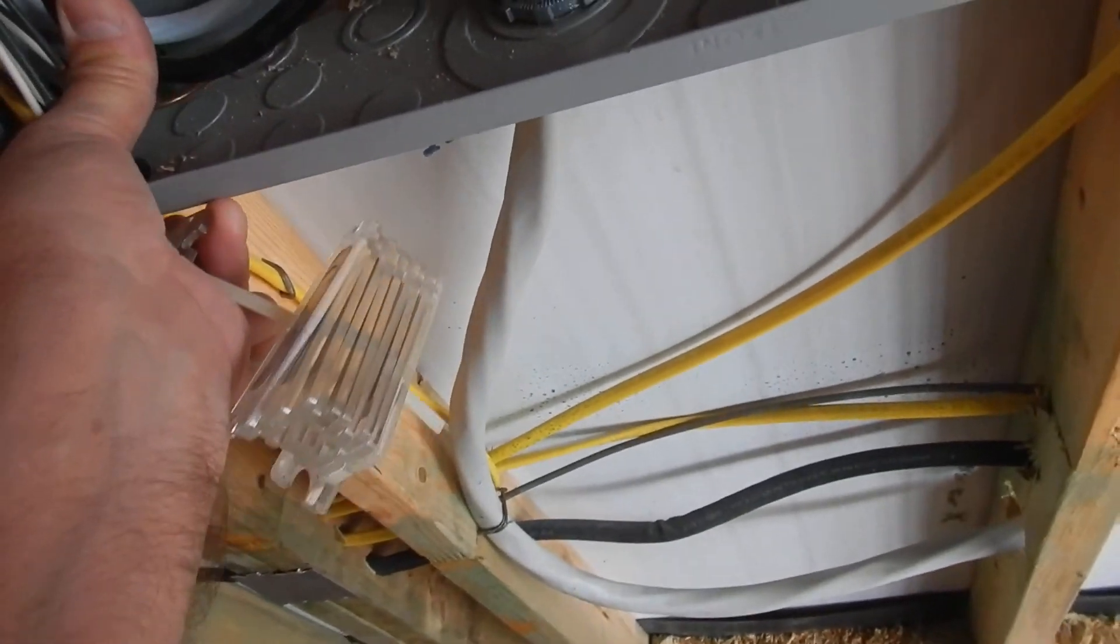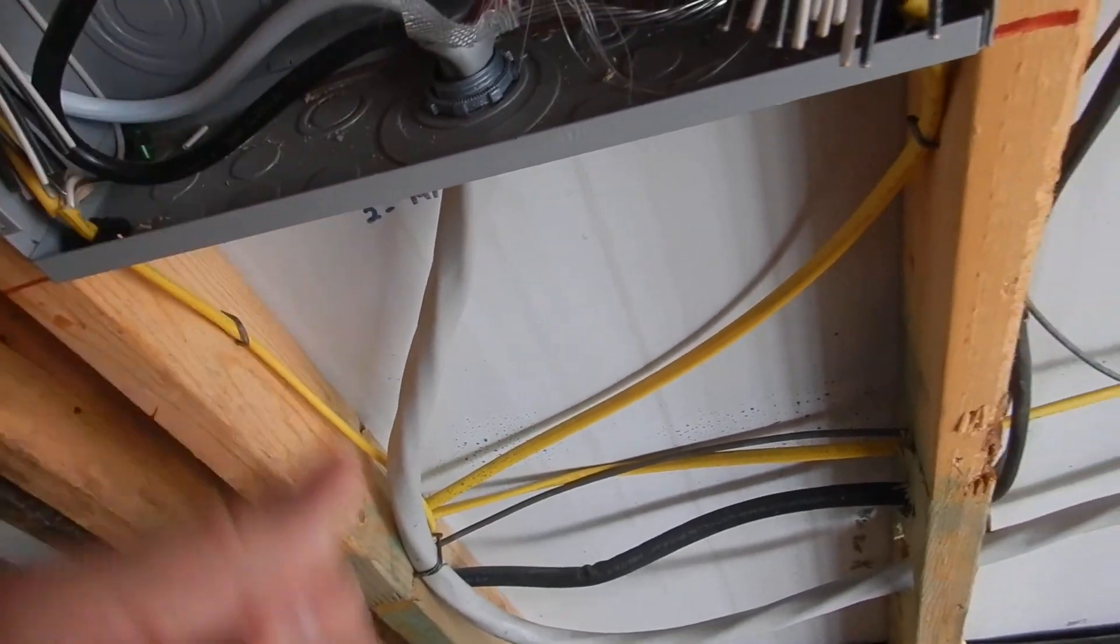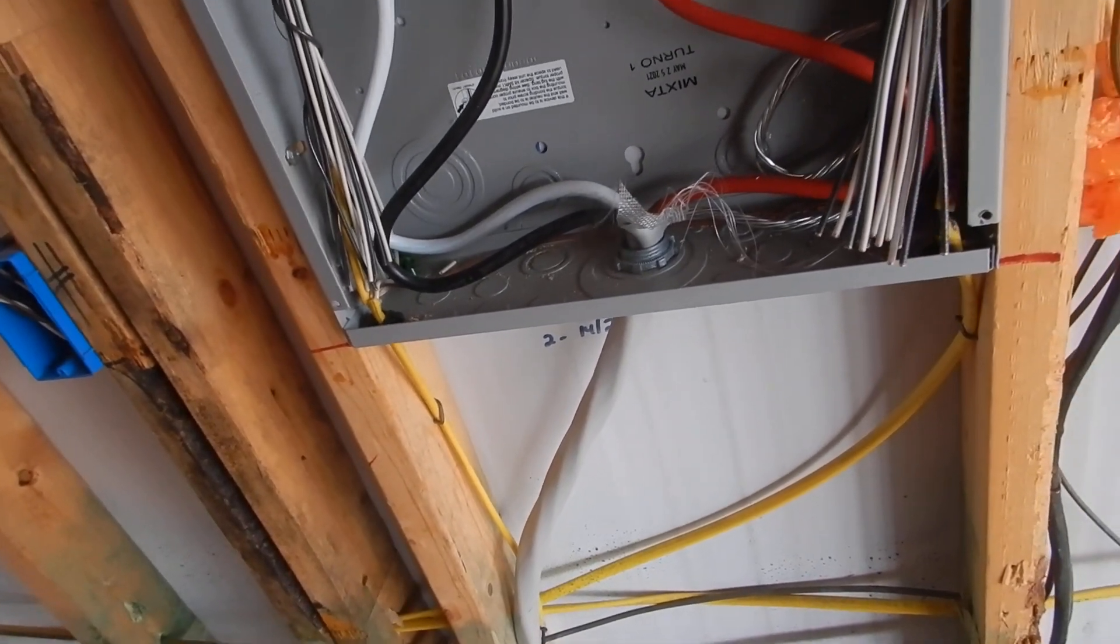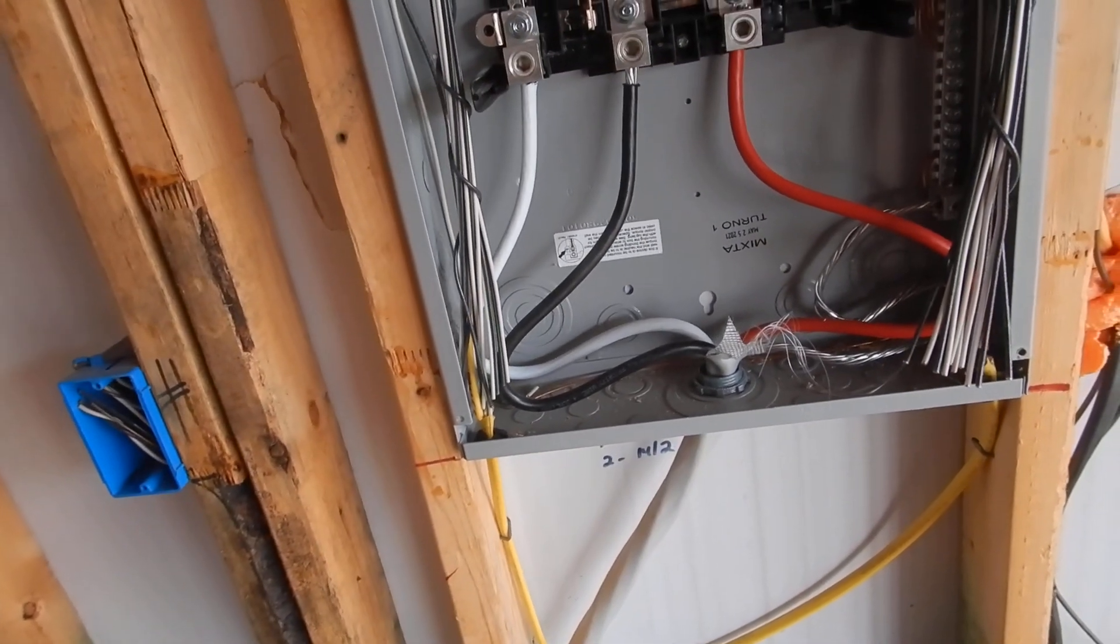Did that fit? That's what I'm seeing. Number two aluminum over here, reading number two. I want to make sure my eyes were working right. Number two stranded conductor aluminum, they're rated for about a hundred amps.